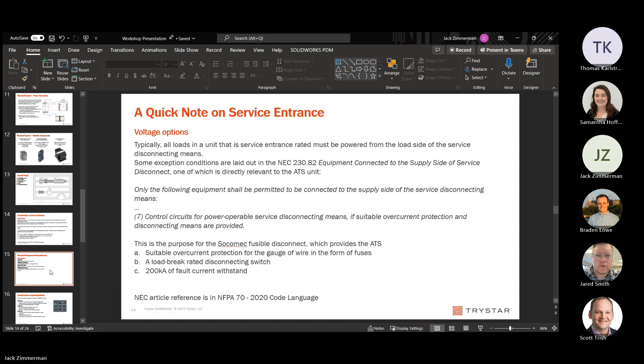Oh, here's just a couple dependencies. I just kind of threw these in. There's a much more laid out one in the Excel document, but all of the components are currently spec'd for 480 in a Y connected system, so 277 to neutral. But this is kind of varying levels of difficulty. As you go down, it gets more and more components. So these should be relatively simple. You have a relatively small voltage to neutral, so you can just spec the components to the neutral voltage.